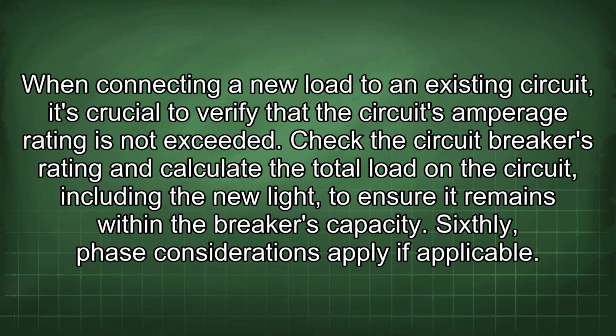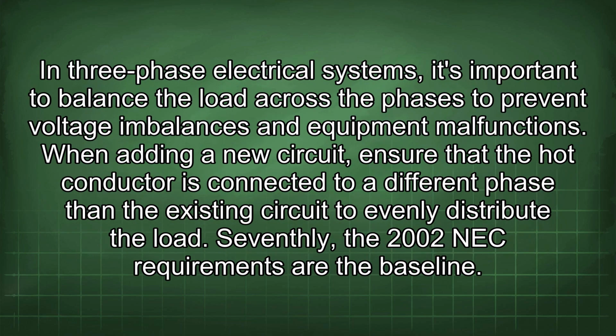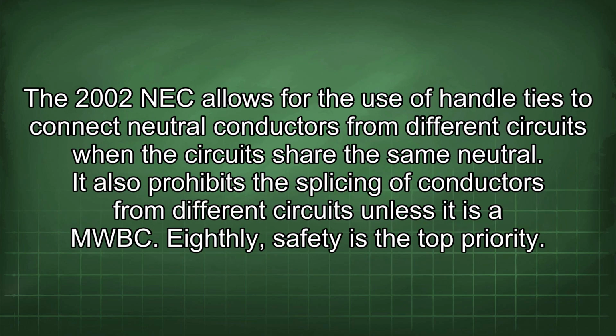Sixthly, phase considerations apply if applicable. In three-phase electrical systems, it's important to balance the load across the phases to prevent voltage imbalances and equipment malfunctions. When adding a new circuit, ensure that the hot conductor is connected to a different phase than the existing circuit to evenly distribute the load. Seventhly, the 2002 NEC requirements are the baseline. The 2002 NEC allows for the use of handle ties to connect neutral conductors from different circuits when the circuits share the same neutral. It also prohibits the splicing of conductors from different circuits unless it is a MWBC.